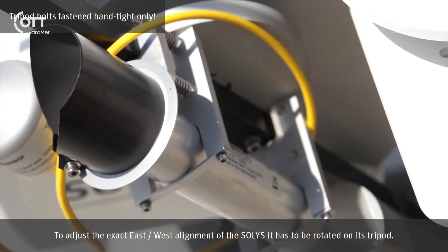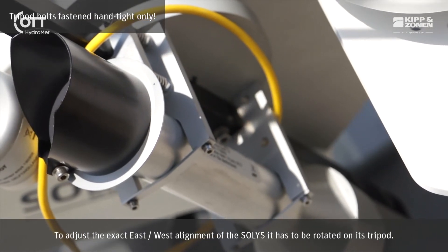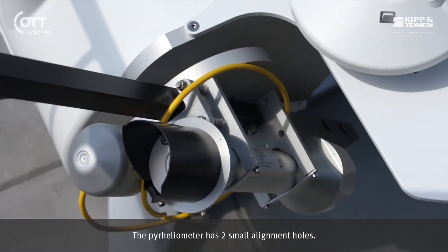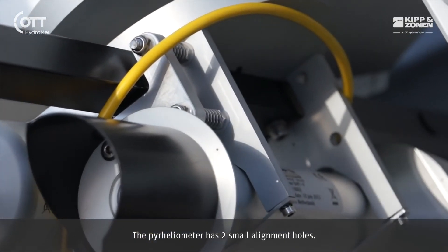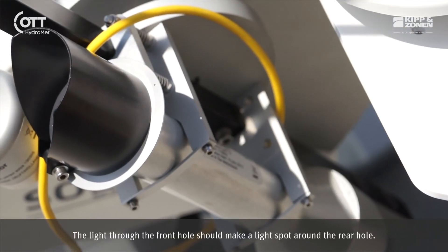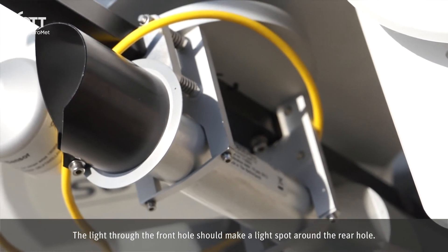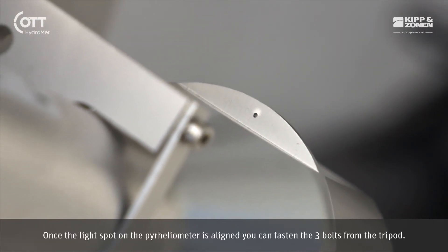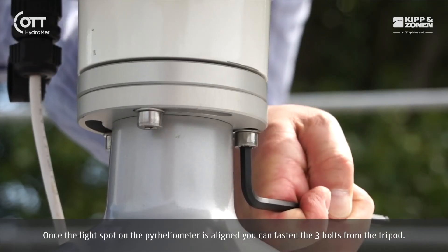To adjust the exact east-west alignment of the SOLYS, it has to be rotated on its tripod. The pyrheliometer has two small alignment holes. The light through the front hole should make a light spot around the rear hole. Once the light spot on the pyrheliometer is aligned, you can fasten the three bolts from the tripod.